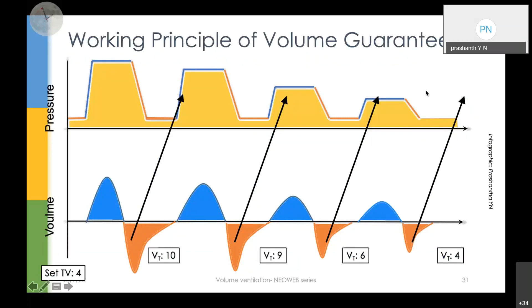All right, so once the tidal volume is achieved, it gives feedback to the machine saying, okay, this is enough. So this is the pressure you need to continue with. Not increasing or decreasing, the ventilator will give this kind of pressure to achieve this tidal volume of 4. All right.